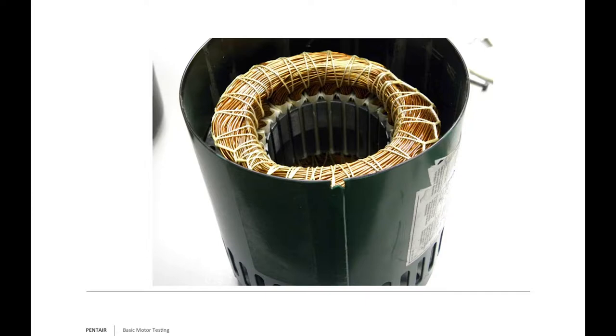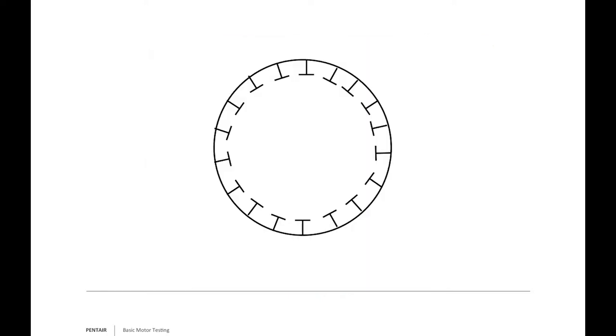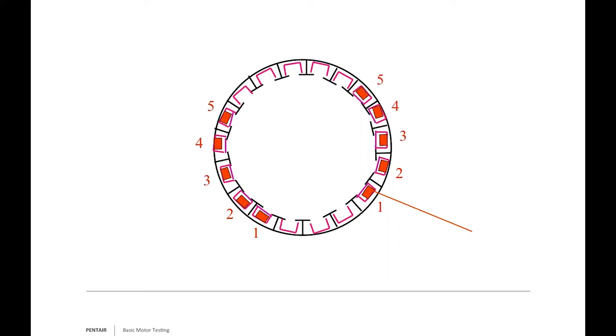Typically, when windings are bad it's a visual inspection—you can measure them, but the visual tells you a lot. In this stator diagram, you have your laminates protecting the wires, and the wires are pressed in at positions one through five—that's your main winding.